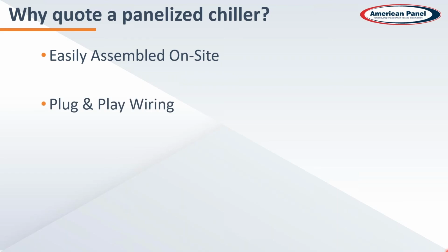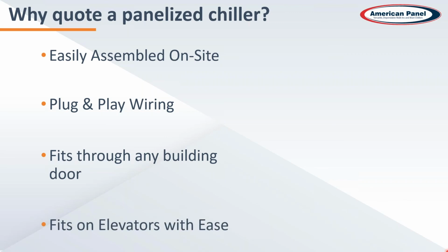Plug and play wiring, it's very easy to set up. You set up the panels just like a walk-in, you put the two electrical pieces together and it's all pre-wired and you just plug it in and hook up the refrigeration and go. Fits through any building door. Like I said, it's hard to get those big units through building doors sometimes on an existing job site. And you can even get it on an elevator. Maybe you're on the 44th floor of a building, you need to get a blast chiller up there. Panelized blast chiller might be the right fit.